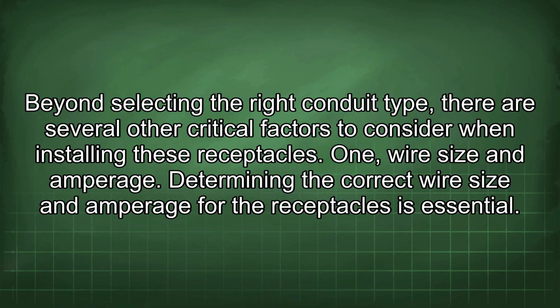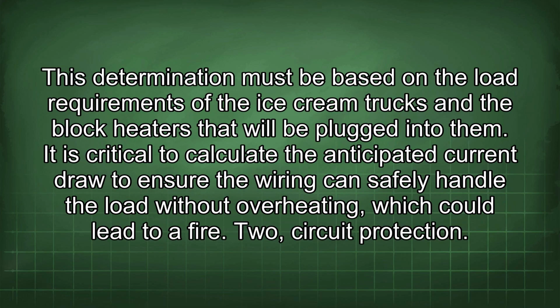1. Wire size and amperage. Determining the correct wire size and amperage for the receptacles is essential. This determination must be based on the load requirements of the ice cream trucks and the block heaters that will be plugged into them. It is critical to calculate the anticipated current draw to ensure the wiring can safely handle the load without overheating, which could lead to a fire.